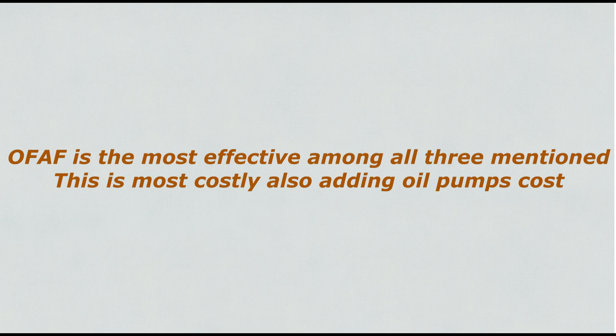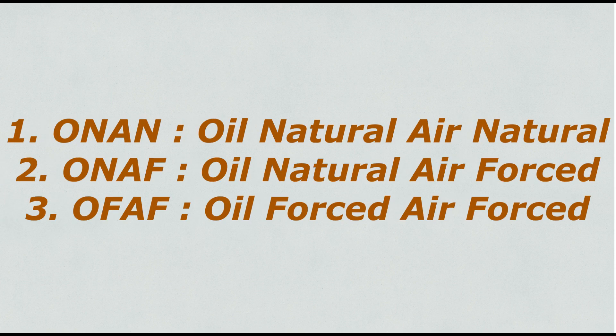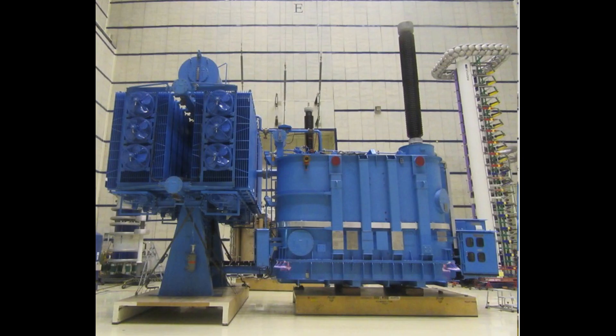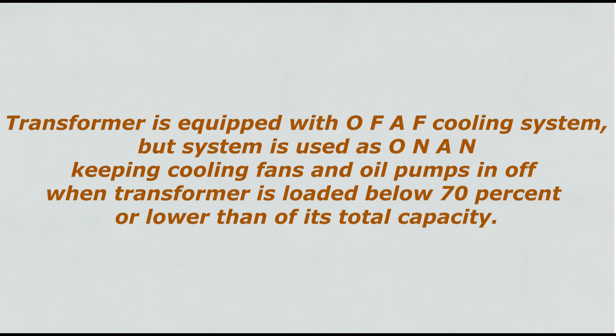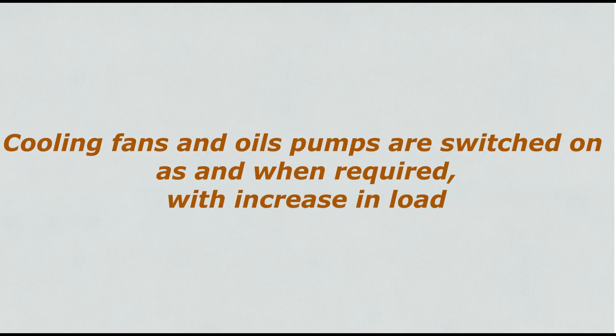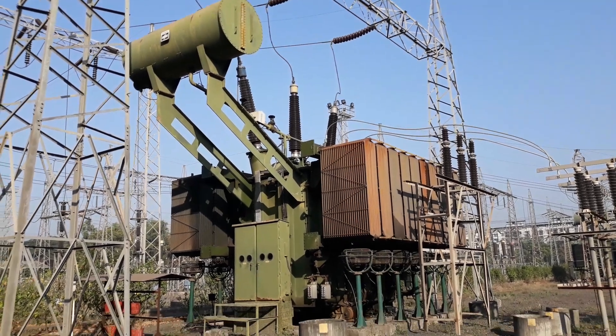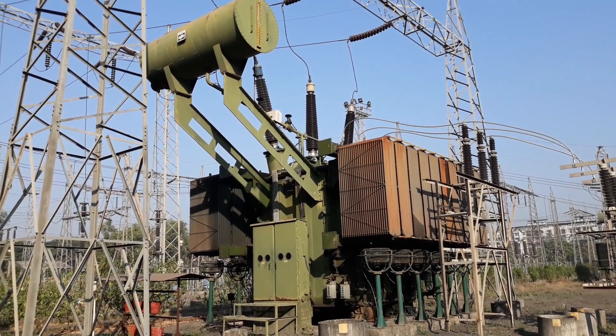This is the most costly system as well, adding oil pump costs. So these are the commonly used cooling systems. In some cases, a transformer is equipped with an OFAF cooling system, but is used as ONAN — keeping cooling fans and oil pumps off when the transformer is loaded below 70% of its total capacity. Cooling fans and oil pumps are switched on as and when required with increase in load.